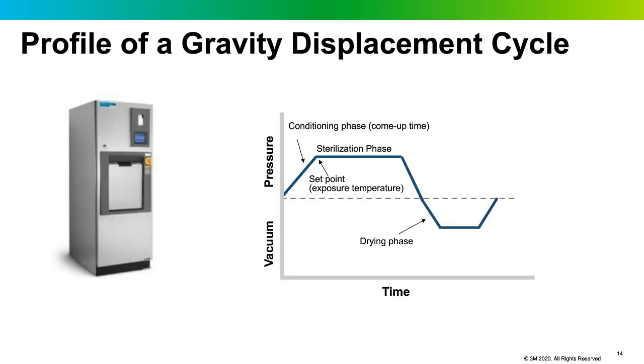In a gravity displacement sterilizer, incoming steam displaces air through a drain near the bottom of the sterilizer during the conditioning phase. When the temperature sensor at the drain reaches the preselected cycle temperature, the drain closes and the exposure phase begins. The cycle finishes with a drying phase. In contrast, a pre-vacuum cycle uses mechanical vacuum to remove air — a series of steam injections followed by vacuum pulls below atmospheric pressure — before the exposure phase, followed by a drying phase.